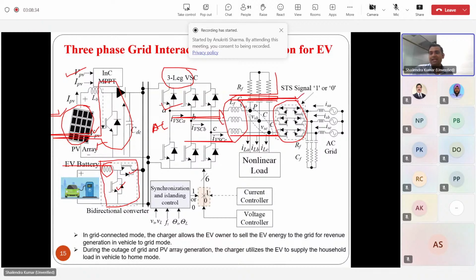In the very first slide, I discussed why these solid state switches are utilized, how the reliability of the system is improved when we are using these static transfer switches. These static transfer switches are able to connect this charger with the grid, and whenever these parameters are not within limit, it can disconnect your charger from the grid, so that if any fault is occurring in the system, your charger should not be affected by that fault.